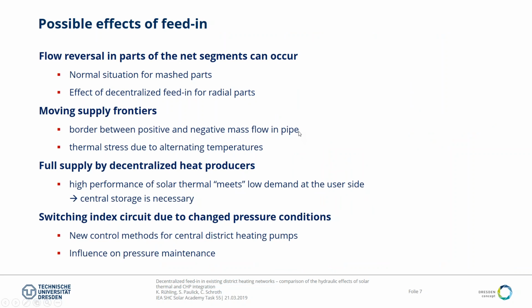What are the possible effects of feed-in on our system, the thermohydraulic effects? We see flow reversals in part of the net segments, and this is a normal situation for meshed parts, but for the radial district heating parts, these are only effects of decentralized feed-in. We also see moving supply frontiers. This means the border between positive and negative mass flows in the pipe. That means the volume flow is roughly 0. And what we want to investigate is thermal stress due to alternating temperatures.